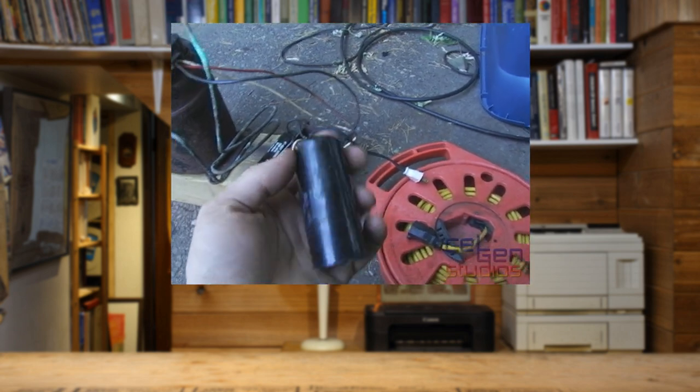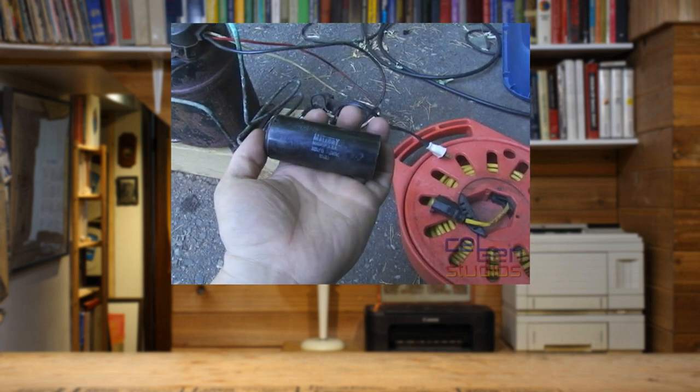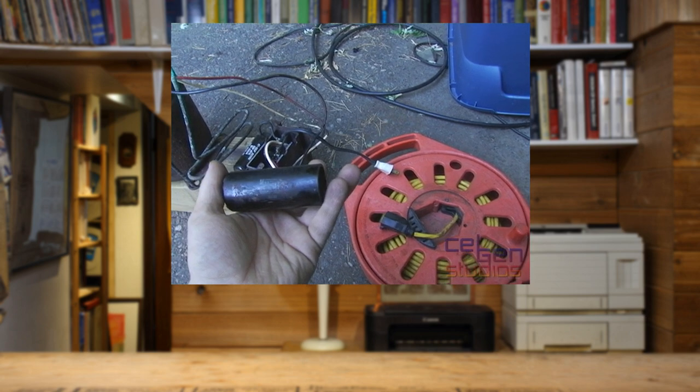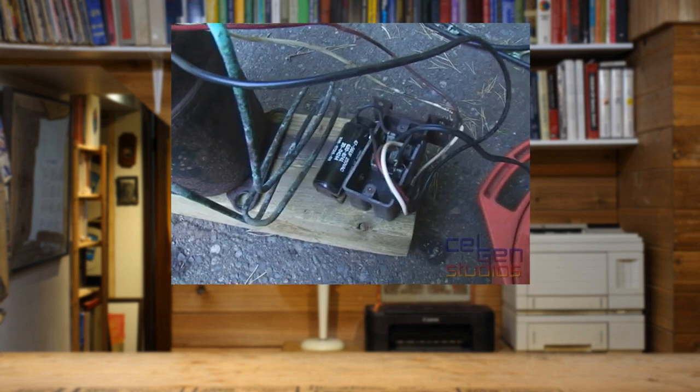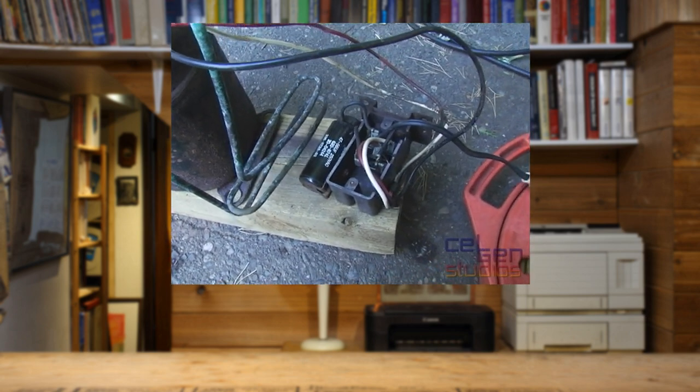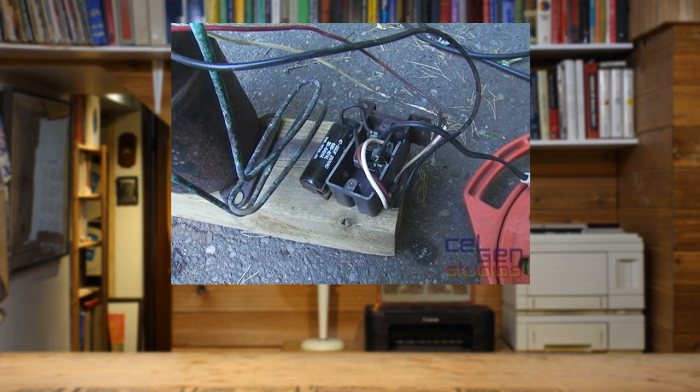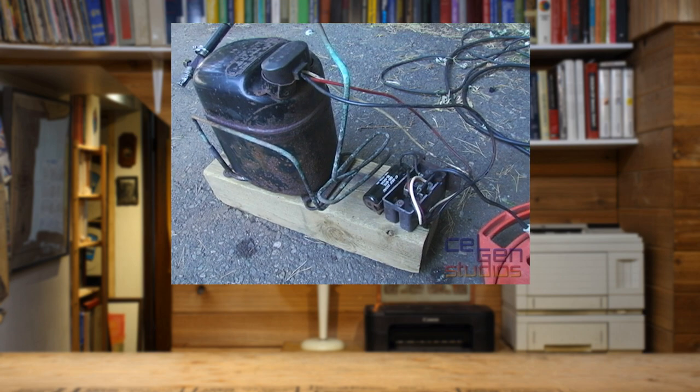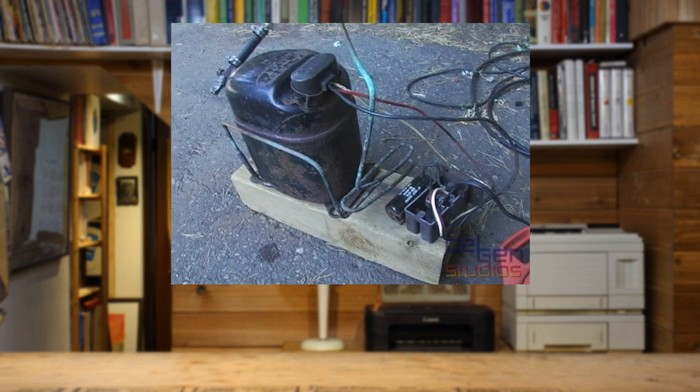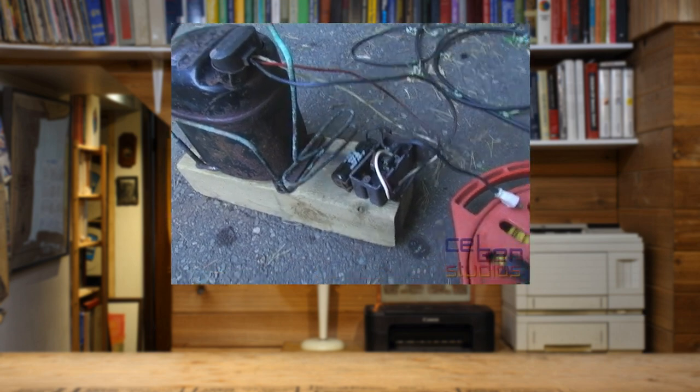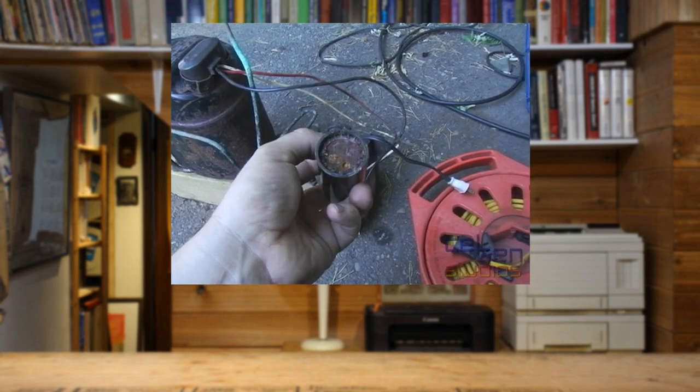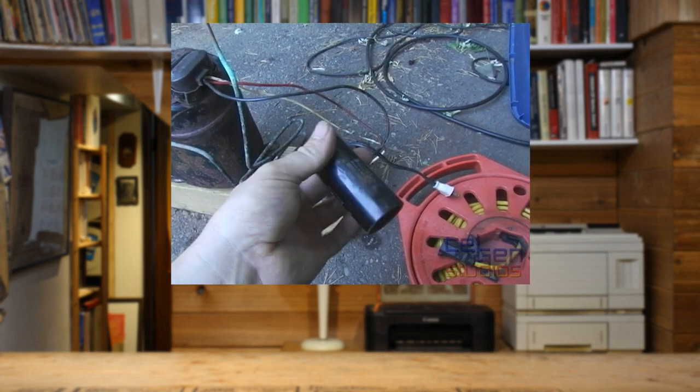And I managed to find another motor start capacitor. This is the original one right here, rated for 165 volts AC, 88 microfarads. The one I found is rated 47 to 56 microfarads, 250 volts AC. Not an absolutely perfect replacement, but what the hell, because the moment I pulled off the original one, the terminals fell off with it. Discovered two things: one, this cap was very much dead.